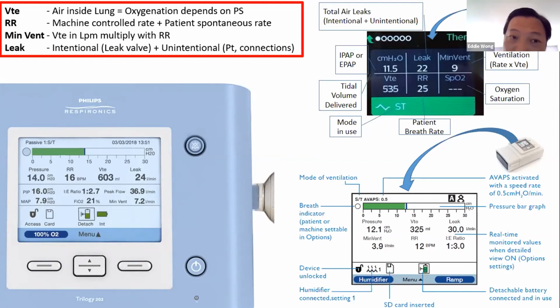That time also we created the unintentional leaks. Normally the leak should fall between 20 to 30 for nasal mask user. It should fall between 25 to 35 for oral nasal mask user. It should fall between 45 to 60 liter per minute for tracheostomy patient. Especially when they open the mouth, the leak will climb up to maybe 60 liter per minute. So you must always monitor the leak so that you know whether all the interface is connected improperly.